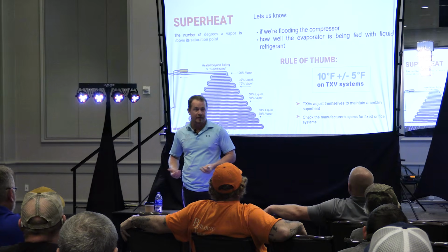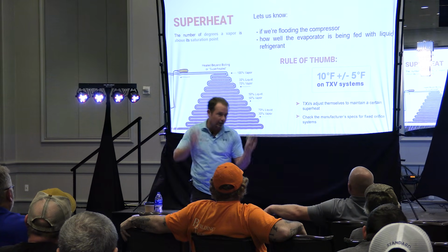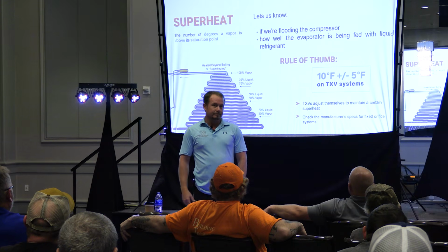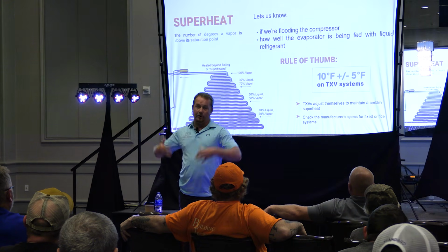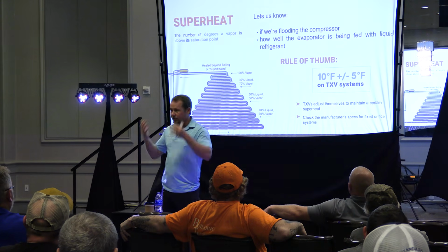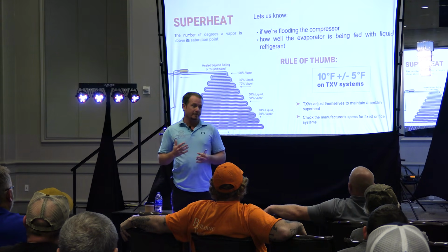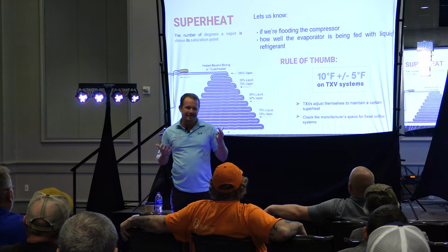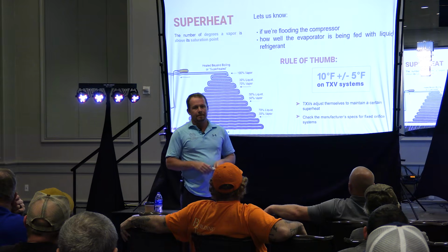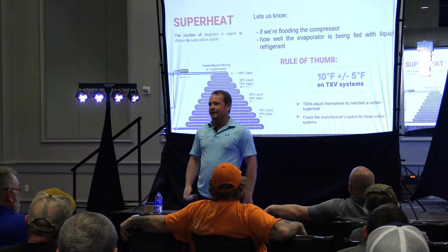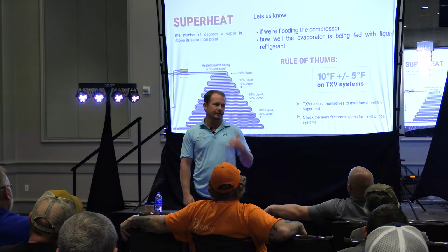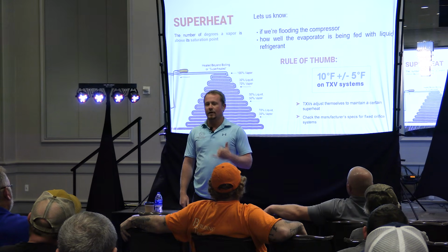You could have a 10-degree superheat and an evaporator temperature that's way lower or way higher than it should be, and that's still a problem. But if you think of it in terms of evaporator fullness with liquid or saturated refrigerant, that's a good heuristic to use. Is it exactly right? Well, yes and no, because there's another major problem. When somebody calls you up and says my superheat is 10, what should be the next question?